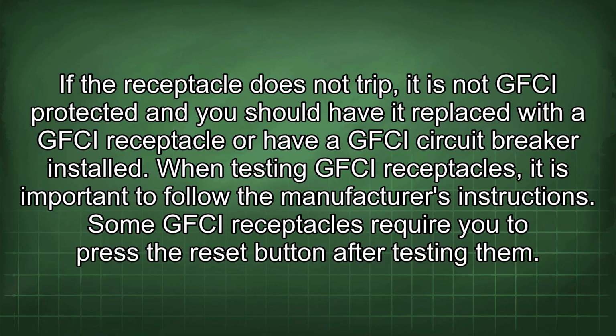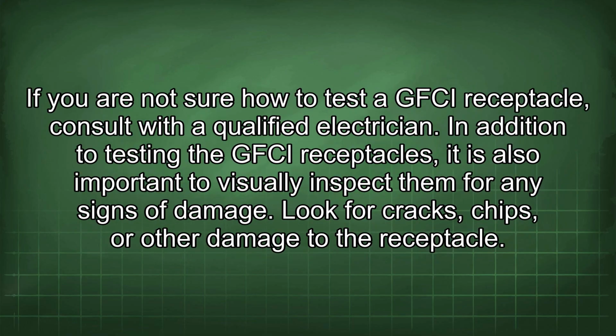When testing GFCI receptacles, it is important to follow the manufacturer's instructions. Some GFCI receptacles require you to press the reset button after testing them. If you are not sure how to test a GFCI receptacle, consult with a qualified electrician.